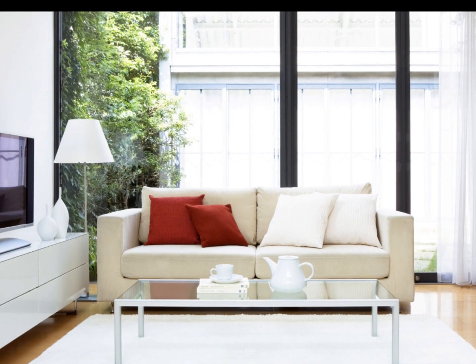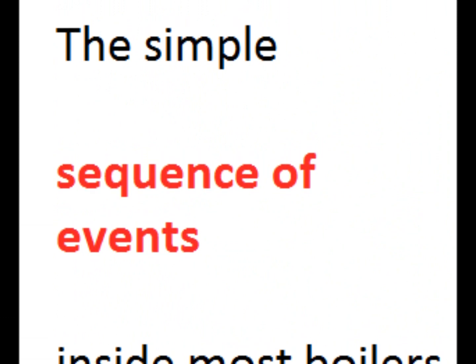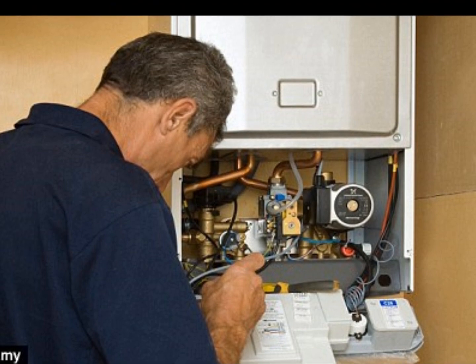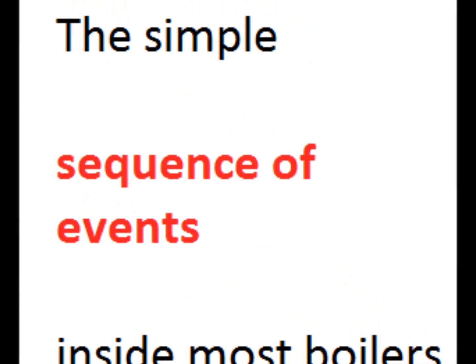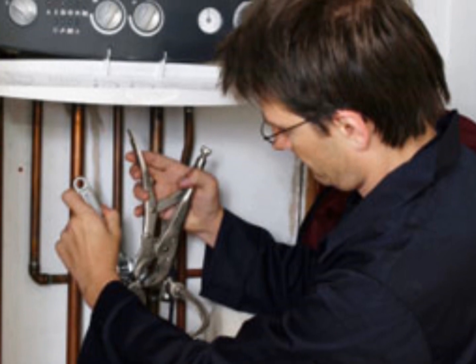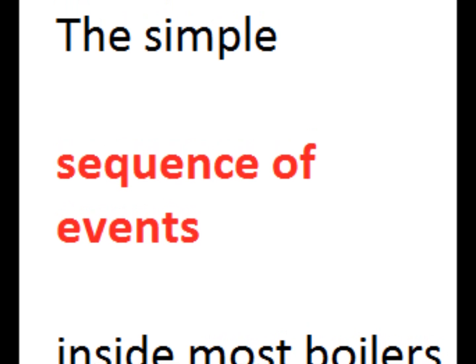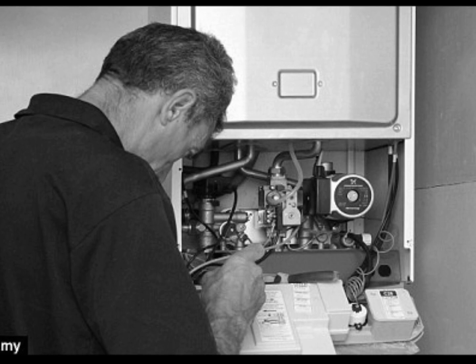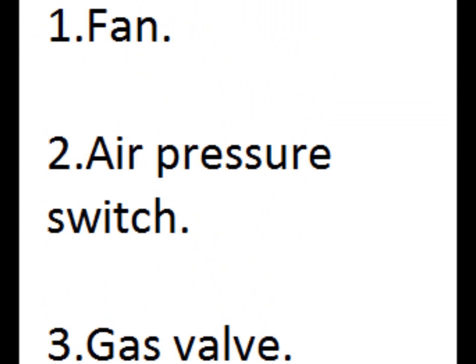This time out we've got a real special one — it's all about the boiler sequence, the sequence of events, what comes next. Obviously, if you can tell the future of what comes next, you'll know how to repair it. For example, if I know after the fan comes the air pressure switch, after that comes this, then I know before that it should be that. It's as simple as that. What is the correct sequence of events? If you know this sequence, essentially you can repair any boiler.